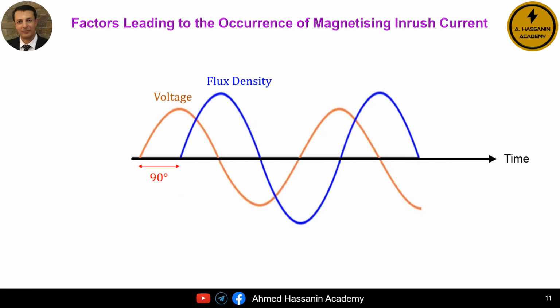Therefore, we must understand that the main reason behind the presence of magnetizing inrush current is the interaction between the supply voltage applied across the primary winding of the transformer and the magnetic flux density inside the iron core or within the magnetic circuit of the transformer. Of course, we all know that under normal operating conditions of the transformer, the magnetic flux wave lags behind the voltage wave by a phase angle of 90 degrees. As I mentioned, this is in the normal case or under standard operating conditions of the transformer. As we can see, the magnetic flux density varies with time in the form of a sine wave, just like the voltage waveform. From this, we understand that the magnetic flux density can also be positive, negative, or 0, depending on the moment in time.